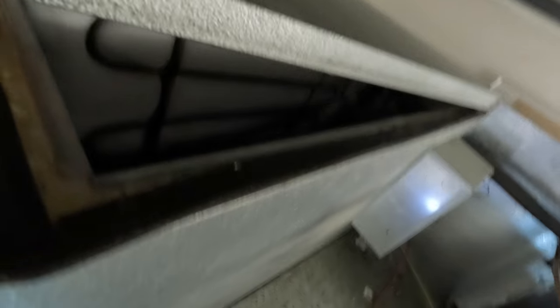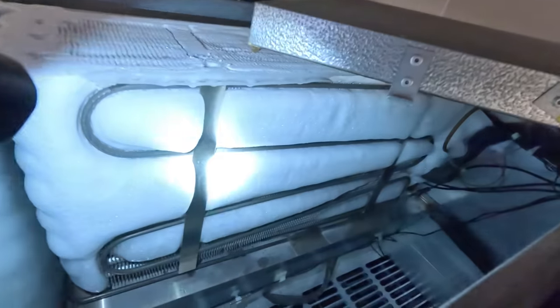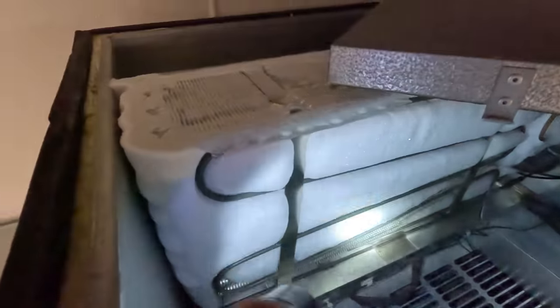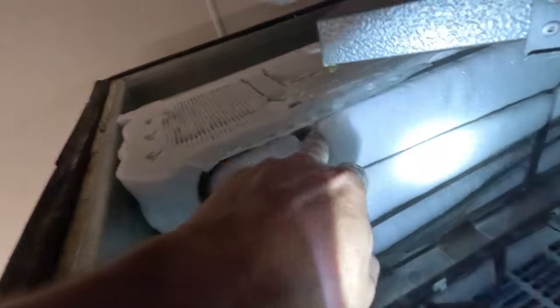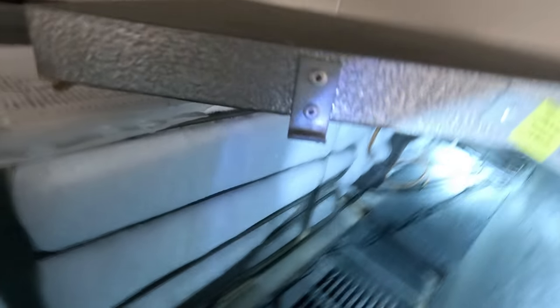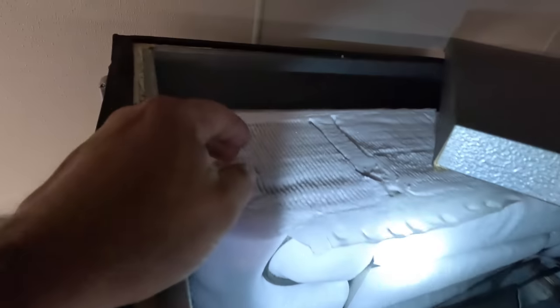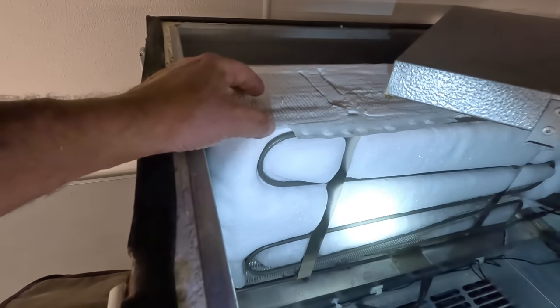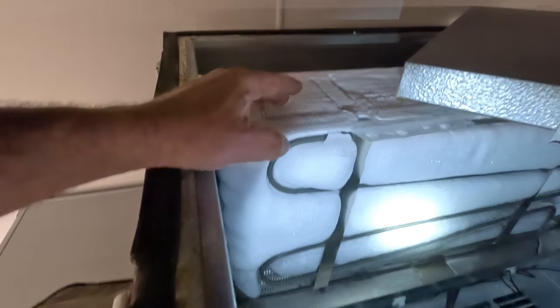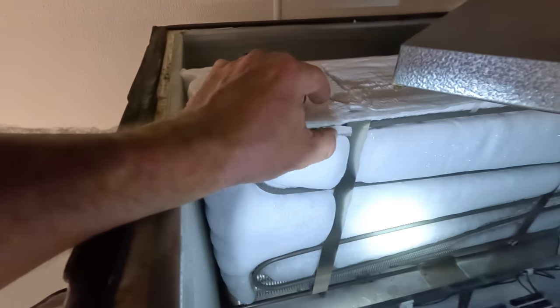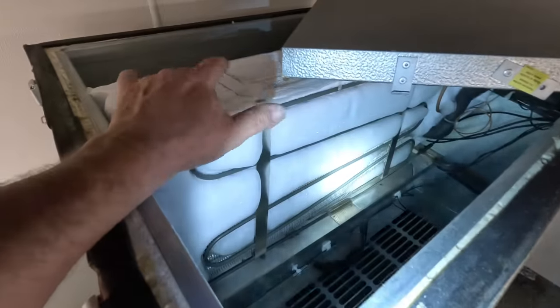Yeah, it was in defrost. Look at this. I can feel the heat on it and you can see where it's melted the coil or melted the ice off. So it's melted it, but the fan's not shutting off. You can see water over there. The fan's never shut down, so it's almost like a total failure on the defrost point. Yeah, like that's melting as soon as it hits it. So let's find out if the contactor's sticking or what's going on. We're going to have to melt this.